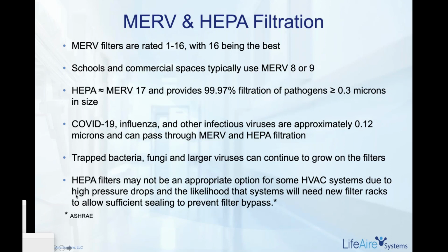And finally, per ASHRAE, which is the governing board really of indoor air quality and ventilation in really all spaces, HEPA filters do add a significant pressure drop. And so if you're looking at retrofitting an air purification solution, this can add a strain to the existing air handler. It may require an upgrade of the air handler, which is an expense. So you need to consider the value of the HEPA filter versus what is necessary to install it, especially if it's an older infrastructure with existing air handlers.